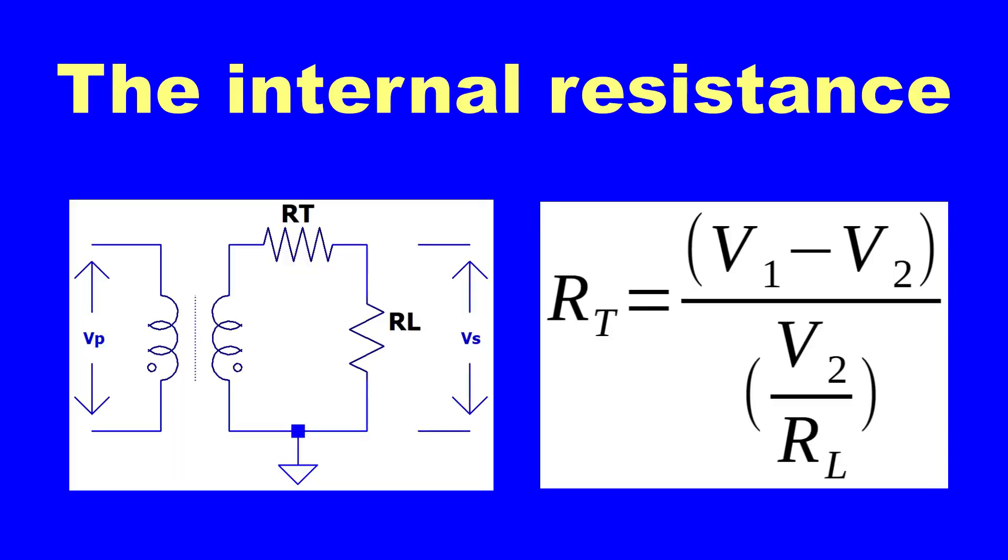Now we calculate the transformer's internal resistance by measuring the voltage drops across different resistive loads. The measurements are taken by recording the value of the connected load, the transformer's no-load voltage, and the voltage under load.